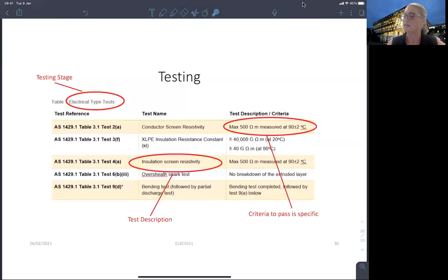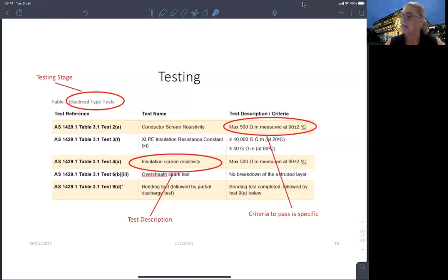You need to show each requirement number and be very specific about what tests are needed and how they pass. This testing stage is the type test, done before the cables are even built in the factory — a sample cable is built and subjected to all of these tests. Some are failure tests, and they need to measure different resistances for the conductor screen at very specific temperatures. These tests are very specific, all per the Australian standards, specifying not just the description but also how they pass.